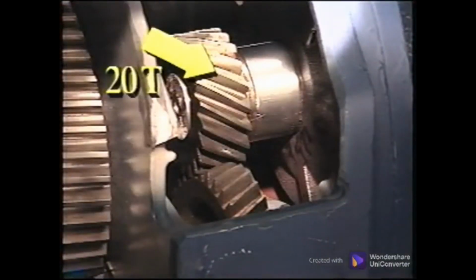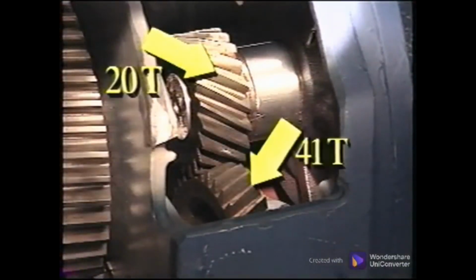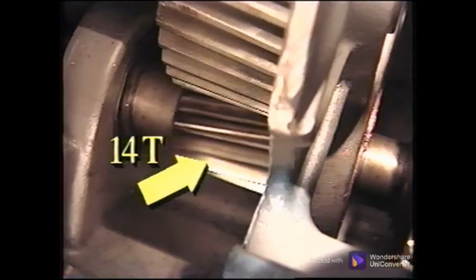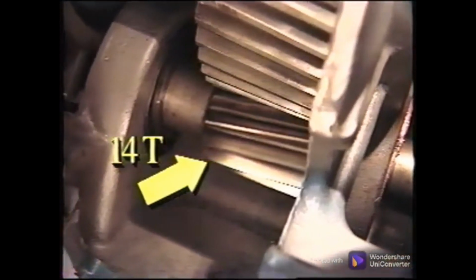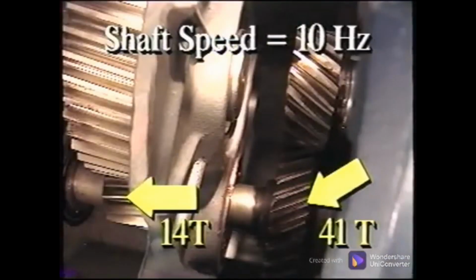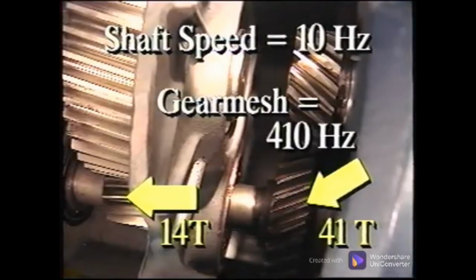This gearbox has 20 teeth on the input shaft and meshes with a 41-tooth gear on the intermediate shaft. These two will have the same gear mesh frequency. But notice that this intermediate shaft has another gear. It has 14 teeth on it. Now the gear mesh will change for this gear and its mating gear. If this intermediate shaft is turning at a speed of 10 hertz, the gear mesh frequency for the 41-tooth gear will be 410 hertz, while the 14-tooth gear would generate a gear mesh frequency of 140 hertz. Multiple reduction gearboxes, such as this one, can be more difficult to diagnose problems due to the additional frequencies generated.